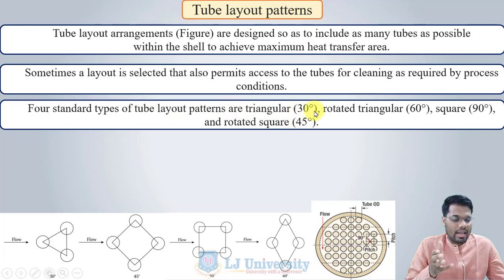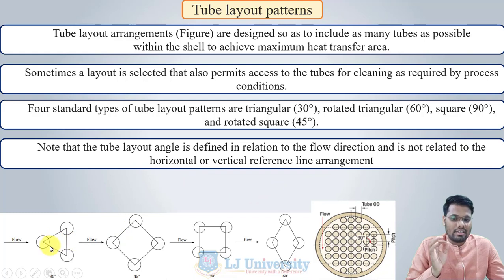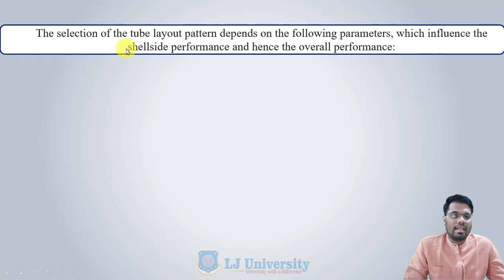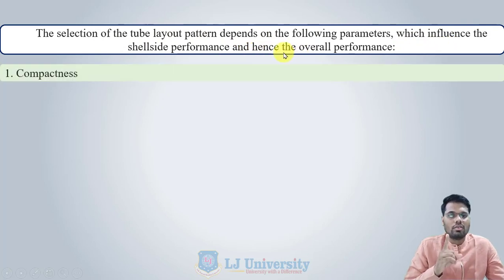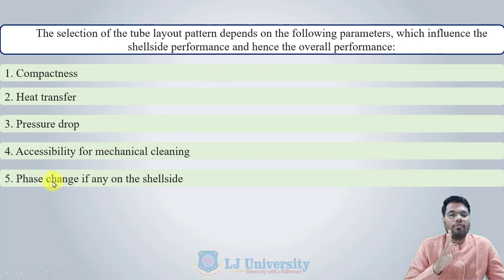The four standard types of tube layout patterns are: triangle (30°), rotated triangle (60°), square (90°), and rotated square (45°). Note that the tube layout angle is defined in relation to the flow direction, not to a horizontal or vertical reference line. The selection of tube layout pattern depends on: compactness, heat transfer rate, pressure drop, accessibility for mechanical cleaning, and phase change if any on the shell side.